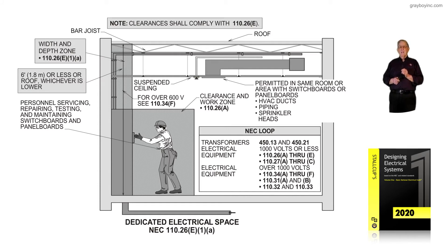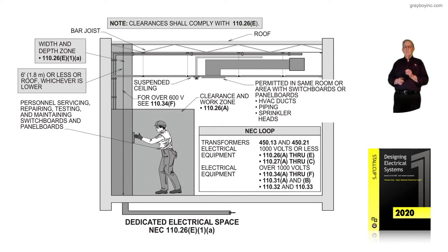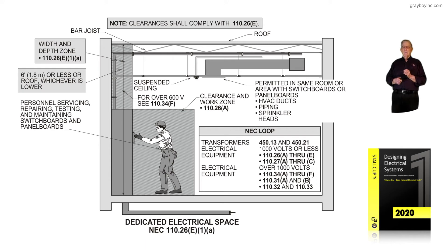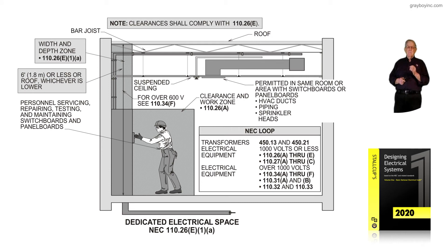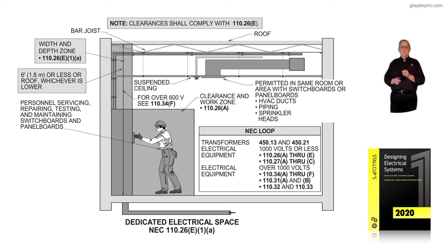110.26A through E deals with your clearances, and 110.27A through C deals with clearances in and around electrical equipment. But notice, over 1,000 volts, we're picking up 110.34A through F, 110.31A and B, and 110.32 as well as 110.33. We're just calling them out so you know that they have to be reviewed if you fall within that voltage level.